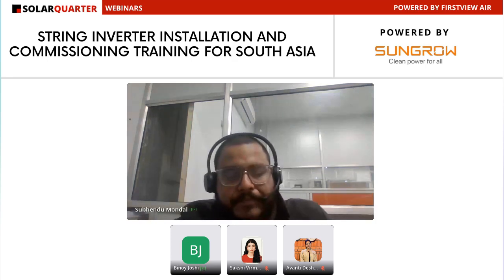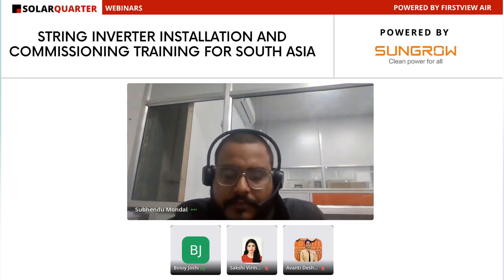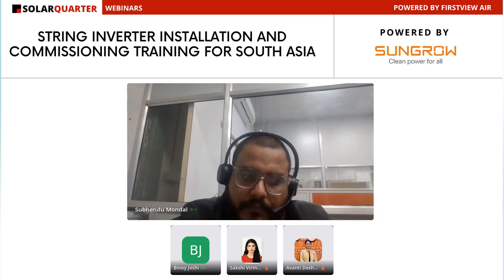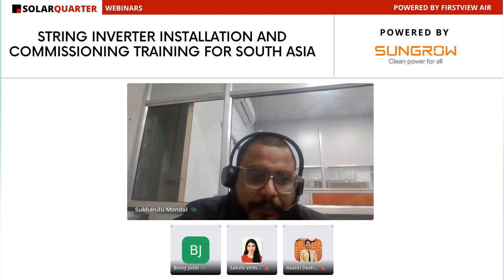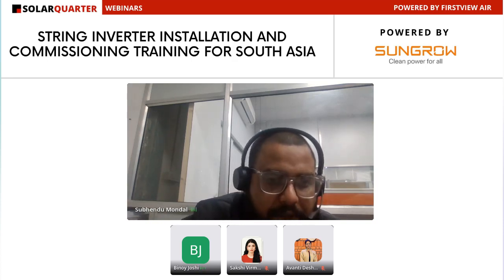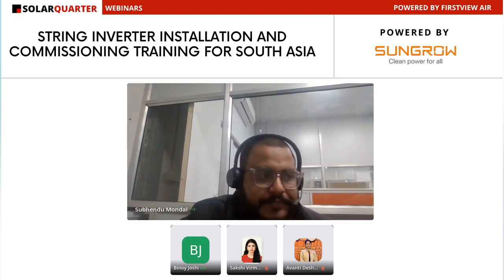Because sir, we are facing lots of issues of inverter tripping on the discom side. Means inverters are tripping. So is there generation loss due to tripping or clipping? Yes sir, tripping, not clipping. Inverter tripping due to over voltage. Okay.